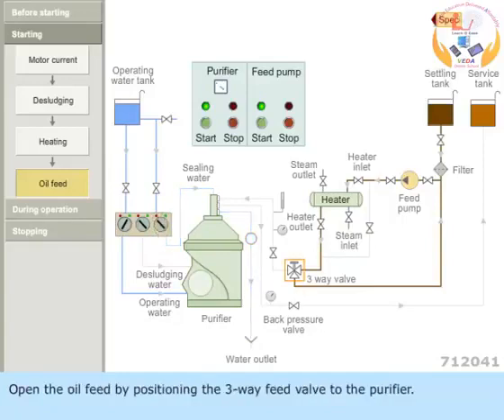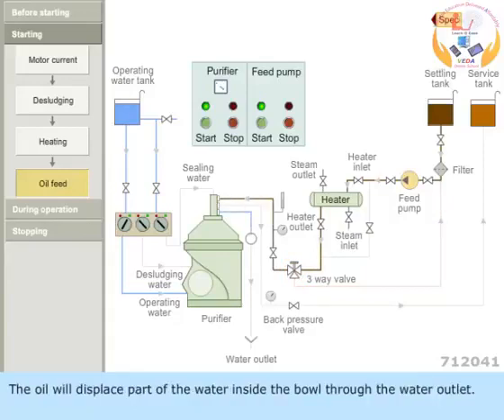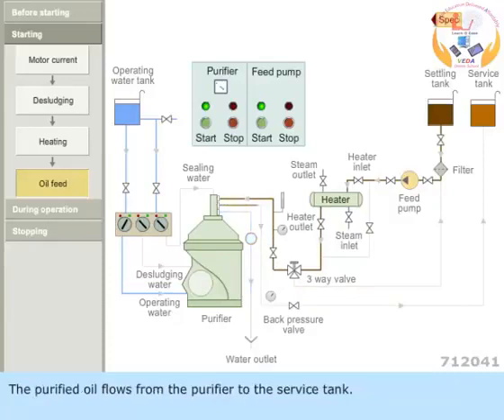Open the oil feed by positioning the 3-way feed valve to the purifier. The oil will displace part of the water inside the bowl through the water outlet. The purified oil flows from the purifier to the service tank.